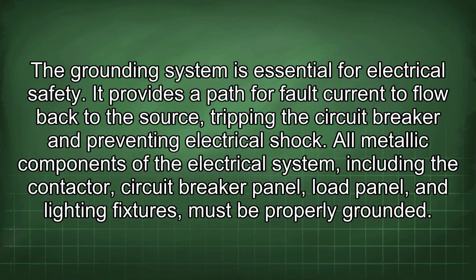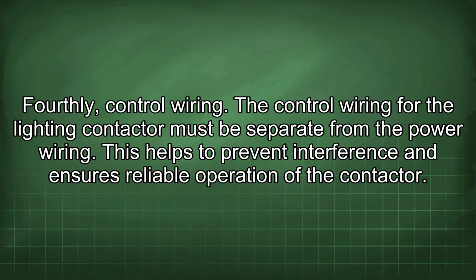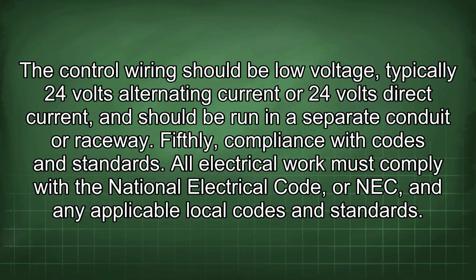Thirdly, grounding. The grounding system is essential for electrical safety. It provides a path for fault current to flow back to the source, tripping the circuit breaker and preventing electrical shock. All metallic components of the electrical system, including the contactor, circuit breaker panel, load panel, and lighting fixtures, must be properly grounded. Fourthly, control wiring. The control wiring for the lighting contactor must be separate from the power wiring. This helps to prevent interference and ensures reliable operation of the contactor. The control wiring should be low voltage, typically 24 volts alternating current or 24 volts direct current, and should be run in a separate conduit or raceway.